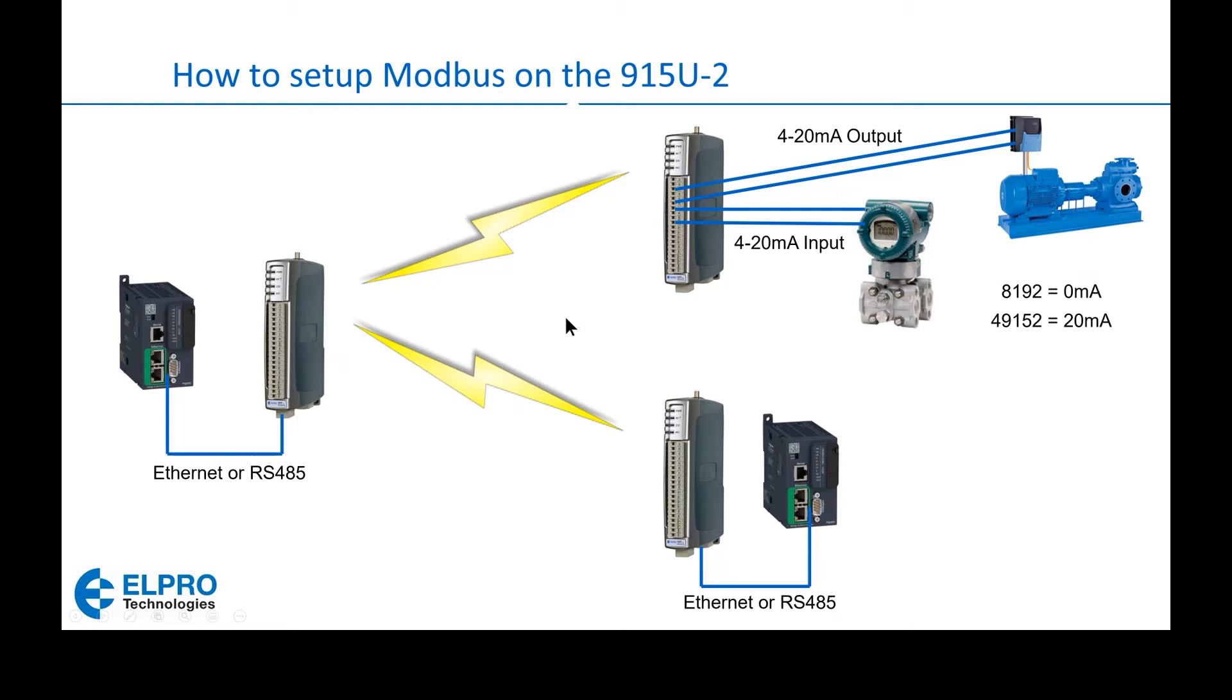An interesting point should be the scaling of the 4 to 20 milliamp values. These are the ELPRO factory defaults: 8192 equals 0 milliamps, 49152 equals 20 milliamps.